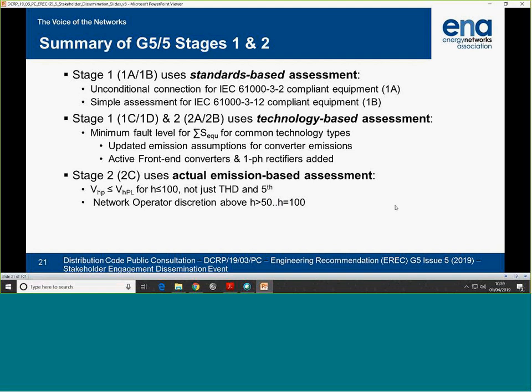Just to say what the stages are under stages 1 and 2. The first two parts of stage 1 are standards-based, making use of the standards that manufacturers have to meet or can choose to meet more accurately. The second part of stage 1 is a technology-based way of doing things: is it pulse, is it active front end, and what kVA you're trying to connect. Stage 1D has a subtlety, using the background measurement of a limiting harmonic to prove the kVA-based, technology-based assessment. And stage 2C is the final stage of assessment. It's similar to what we had before, but more refined.